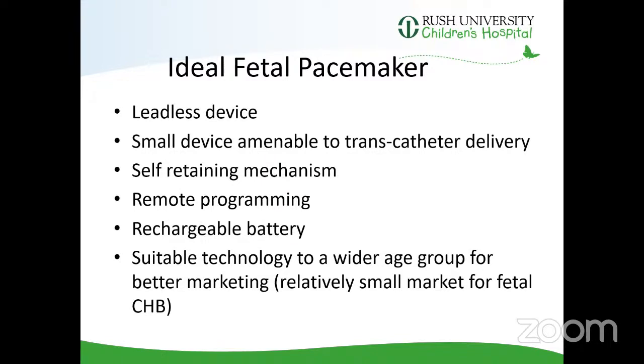It should definitely be a leadless device, because you don't want the fetus, with its movement, to be entangled in all of these leads and then get a lot of injuries. It has to be a small device, and it should be amenable to percutaneous catheter delivery, as we noticed in this group from California. And it should be a self-retaining mechanism with remote programming, and it should have no external battery or connection to an external device. It should be a whole device placed and left there, and it could be remotely programmed.